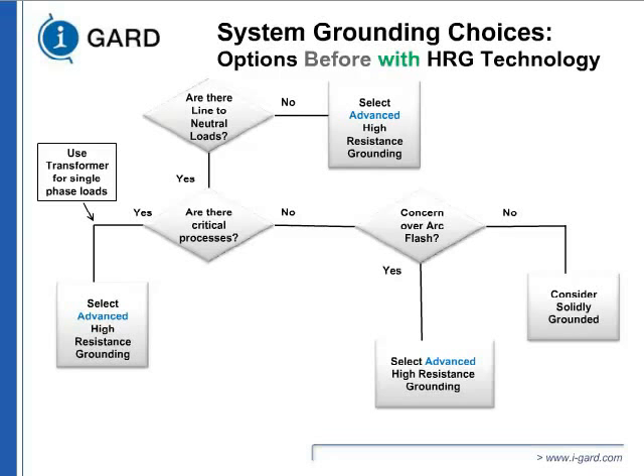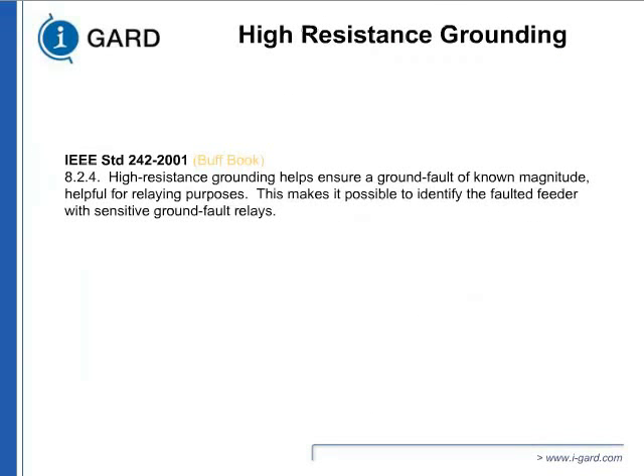This is a Buff Book quote again, in the 2001 version. You can see we are learning. I'm also part of the Buff Book. High-resistance grounding helps ensure a ground fault of known magnitude. Now I know wherever my resistor is set, 1 amp or 2 amp, depending on the charging current, that's the current I have to handle. And if you look at the last sentence, this makes it possible to identify the faulted feeder with sensitive ground fault relays. You can use pulsing, or the relay I showed you with the zero sequence CTs will probably detect that for you.